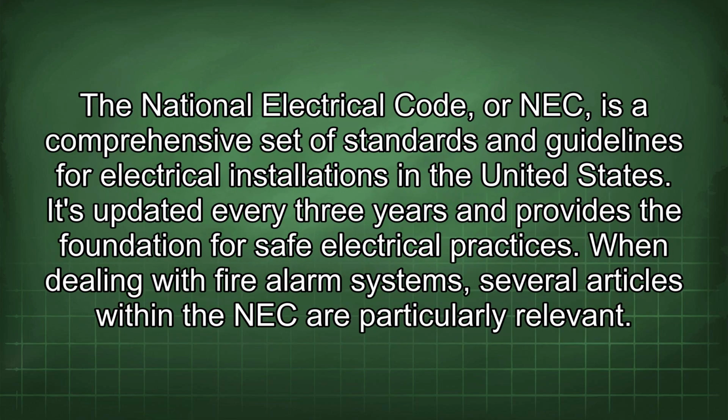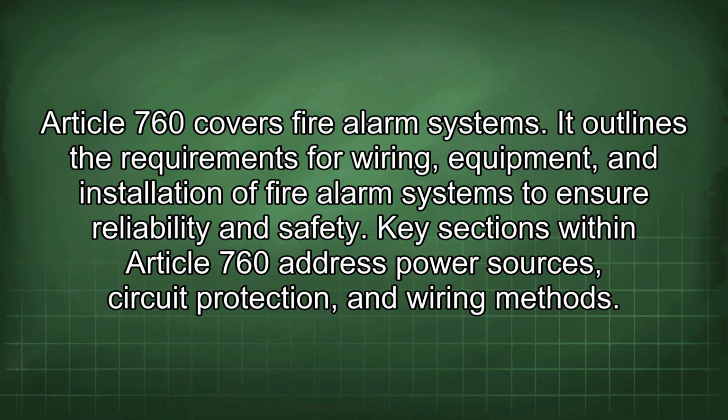The National Electrical Code, or NEC, is a comprehensive set of standards and guidelines for electrical installations in the United States. It's updated every 3 years and provides the foundation for safe electrical practices. When dealing with fire alarm systems, several articles within the NEC are particularly relevant. Article 760 covers fire alarm systems. It outlines the requirements for wiring, equipment, and installation of fire alarm systems to ensure reliability and safety. Key sections within Article 760 address power sources, circuit protection, and wiring methods.